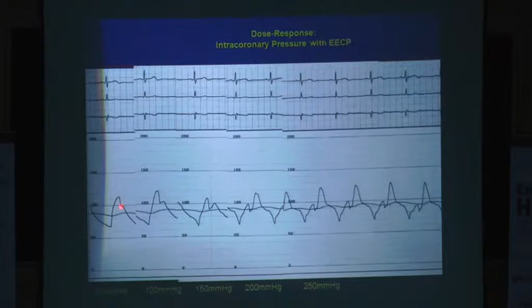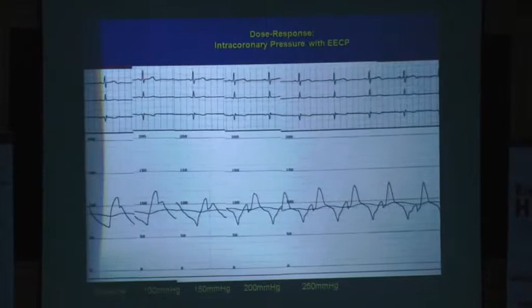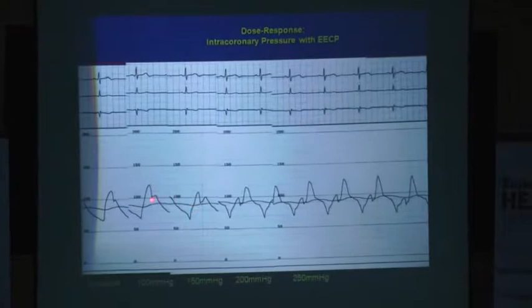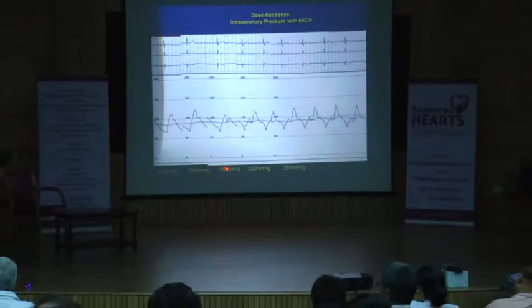So you all know this is a measurement of a pressure waveform. You have a systole, you have the dicrotic notch, the aortic valve closing, and the downsloping diastole. So what happened is, they started giving pressure of 100, 150, 200 and 250, slowly increasing the pressure in the lower leg by the cuff inflation. So that translates into an incremental increase in the diastolic augmentation. You can look at the diastolic. There is a small bulge at 150. By the time they went to 250, the diastolic augmentation is greater than even the systolic pressure.